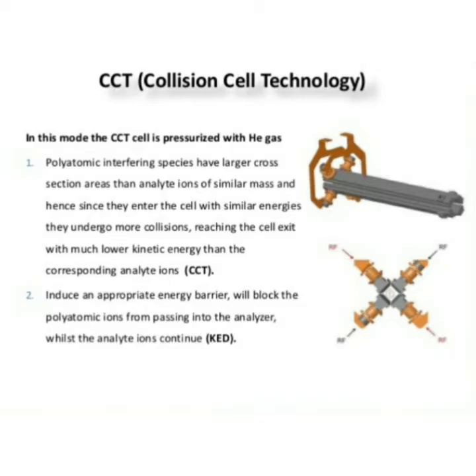What is the CCT mode? Collision cell technology mode. In this mode, the cell is pressurized with helium gas. Polyatomic interfering species have a larger cross-sectional area than analyte ions of a similar mass, and hence, since they enter the cell with similar energy, they undergo more collisions, reaching the cell exit with much lower kinetic energy than the corresponding analyte ions. This is called CCT.